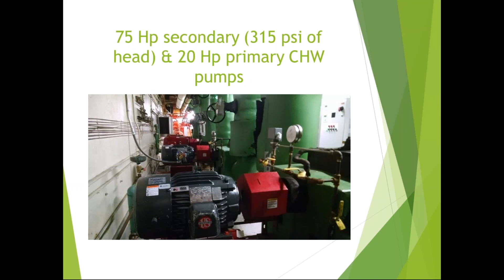Also, what I learned about head pressure in a high-rise building, Tim understands this with high pressures. The tallest building I had before was 38 stories, but it didn't have a chilled water riser. So when I changed motors out for an upgrade recently on my primary systems and frequency drives, I needed to upgrade from a normal drive to one made for something like a conveyor, for concrete or mining type applications. The head pressure on that shaft was so hard to torque on startup that the first drive I put in wouldn't even turn. That's a lesson learned, I didn't know that before since I hadn't dealt with pressures that high with frequency drives.